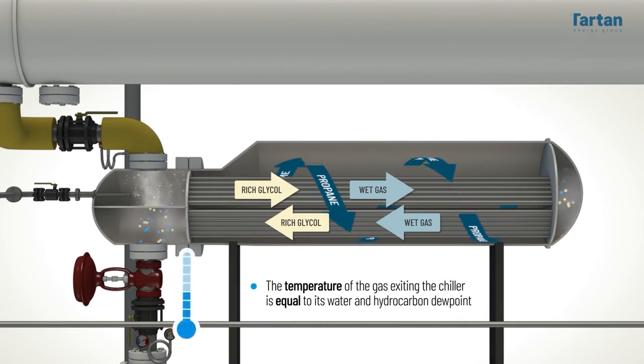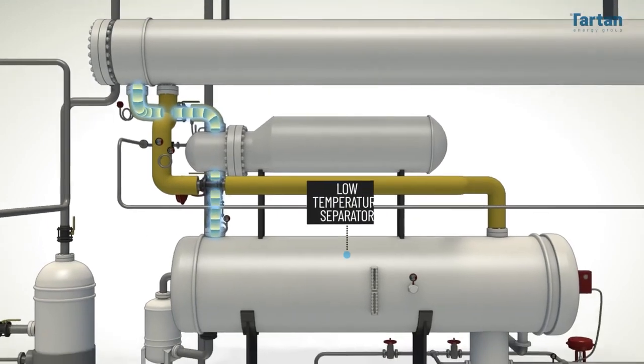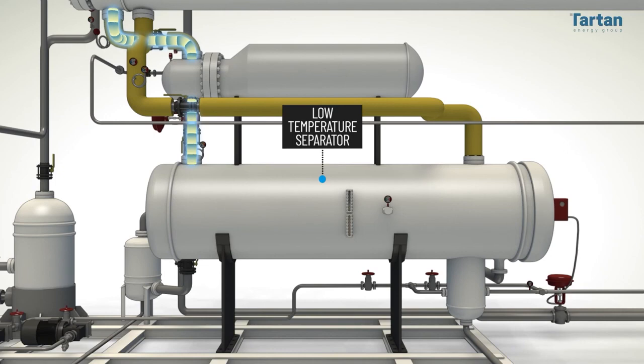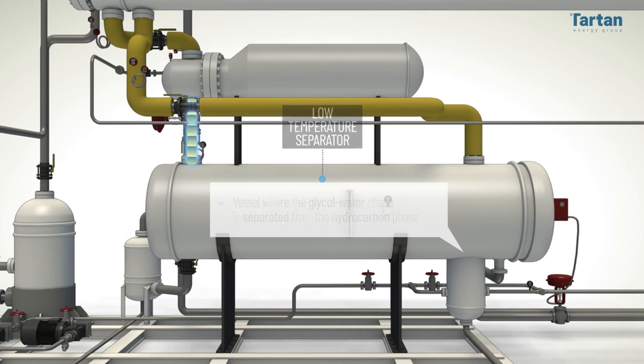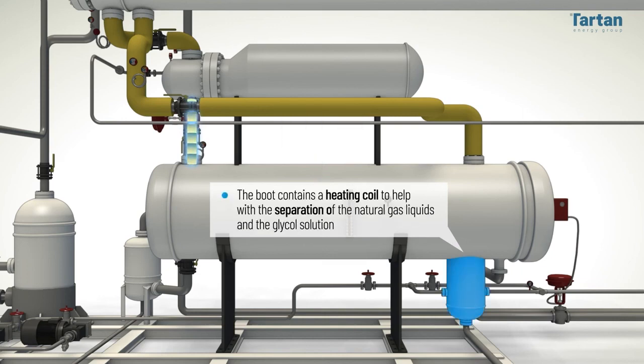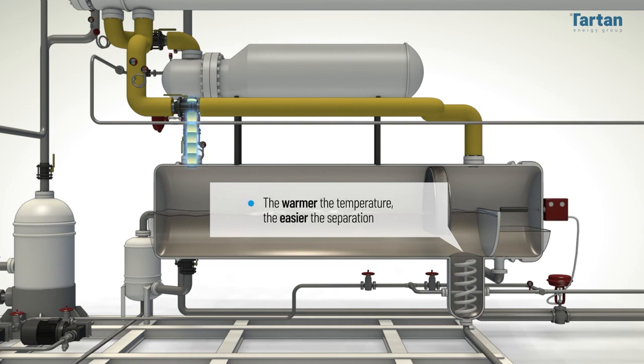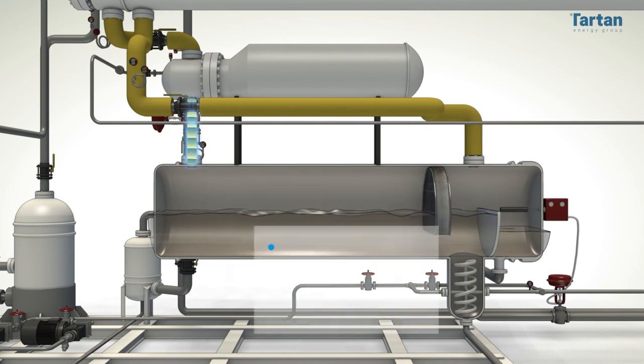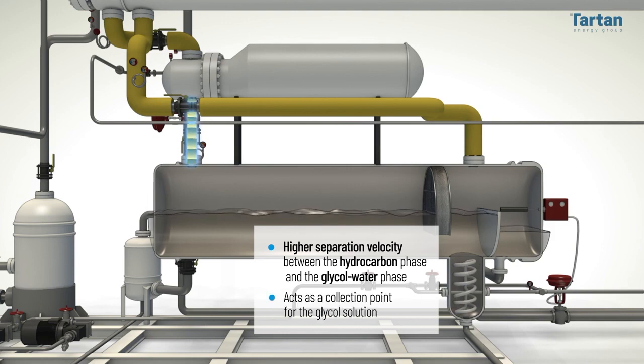Theoretically, the temperature of the gas exiting the chiller is equal to its water and hydrocarbon dew point. Downstream from the propane chiller is the low-temperature separator, or LTS, the vessel where the glycol water phase is separated from the hydrocarbon phase. There is a boot below the LTS, which typically contains a heating coil to help with the separation of the natural gas liquids and the glycol solution. The warmer the temperature, the easier the separation. The boot allows for higher separation velocity between the hydrocarbon phase and the glycol water phase and acts as a collection point for the glycol solution.